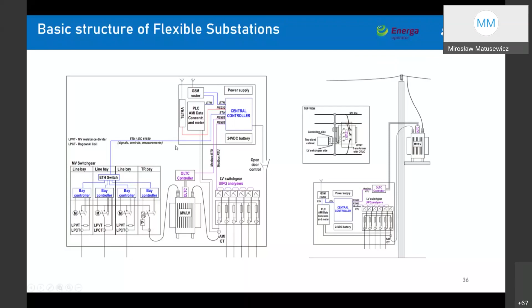On the old substation, we use an AMI system with a data concentrator, built in the same place, and AMI lets us connect with customer meters using PLC protocols. So we can use the voltage deep in the network to know the voltage in the grid. We don't know it in the typical way, but through the AMI system connected with the AMI controller. The timing wouldn't be good if we had to ask the central system for the voltage at each meter.